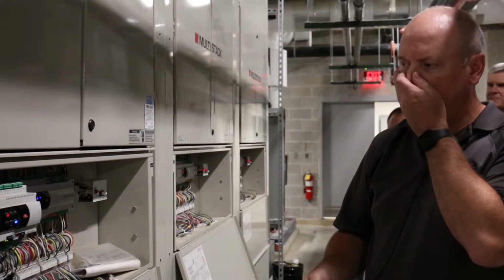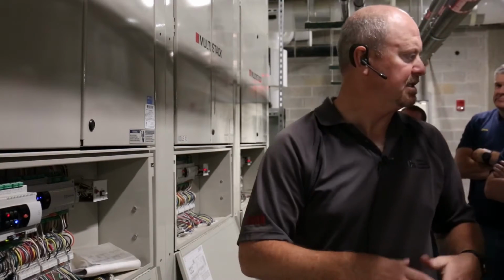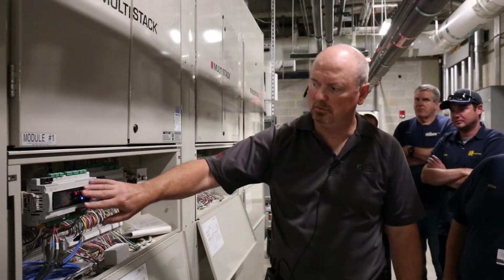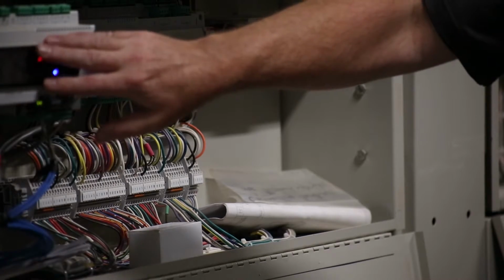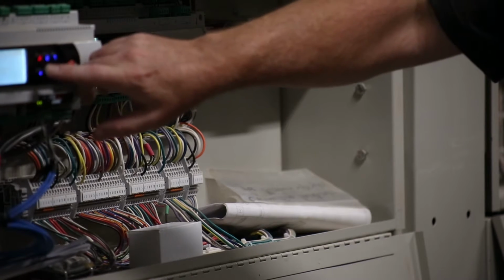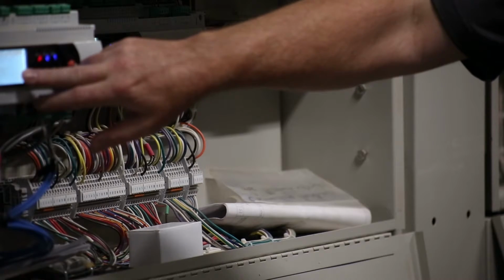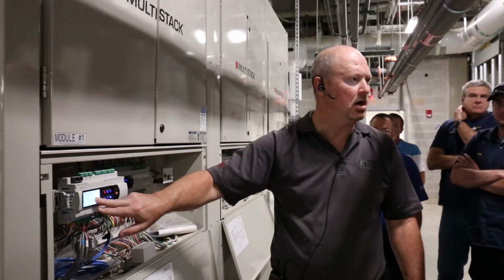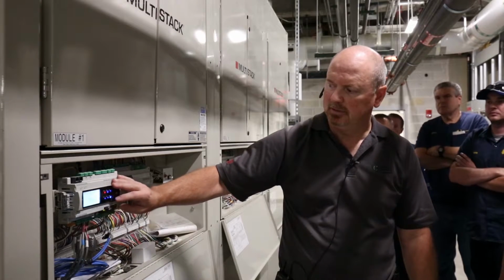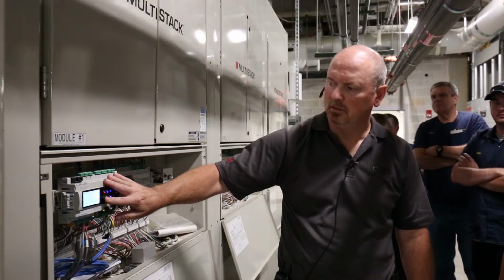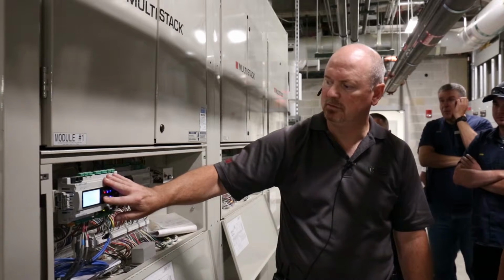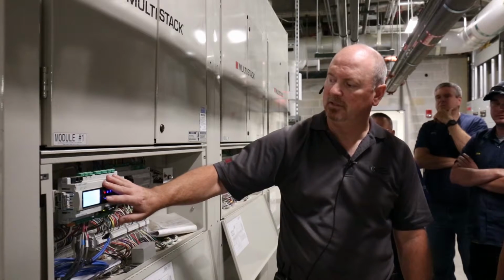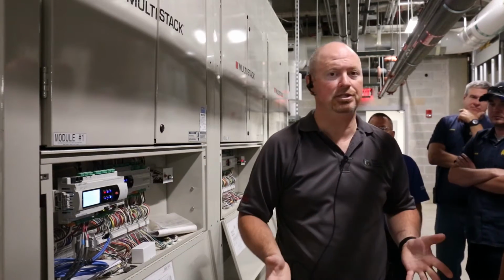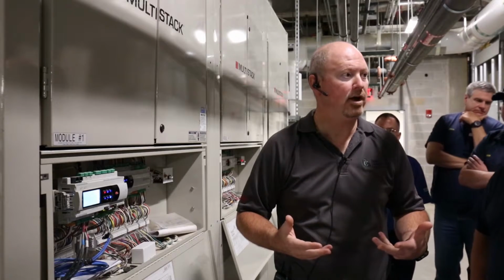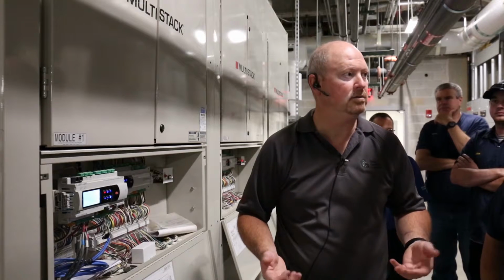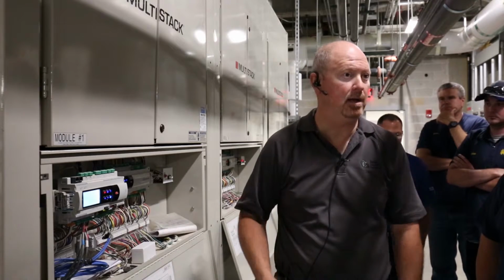So right now, it looks like we have an alarm on the chiller. And this is something that a lot of guys don't know. To get to your alarms, to clear the alarms, you hit the alarm button, it lights up, and you can see what your alarms are. You could have 1 or 2 alarms at a time. Looks like you've got high pressure on this one, high pressure again. Usually it resorts to a flow issue because you don't have enough water flow to cool down the water, so it trips on high head pressure.